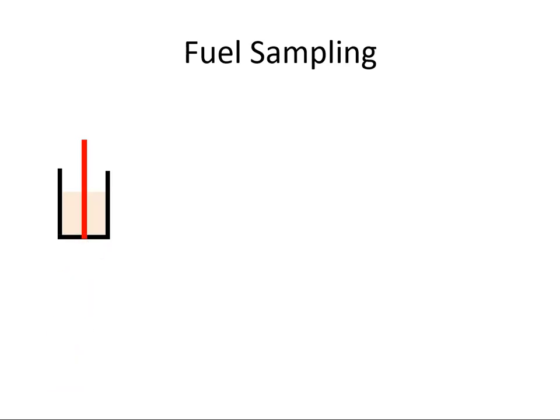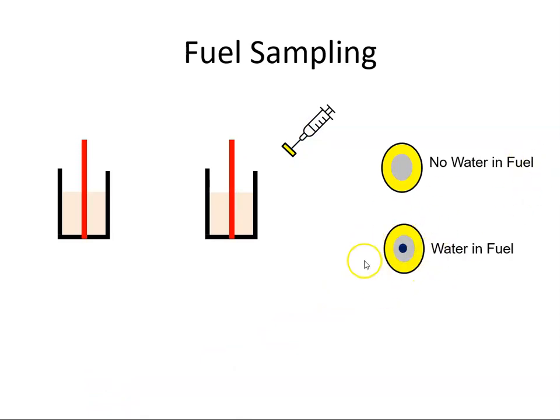If there was no visual indication of water in the fuel, you can do another test with a syringe and a water detection capsule. Put the detection capsule onto the syringe and then into the sample jar. Mix it around and draw the fuel through the capsule into the syringe. If there was any water in the fuel, there will be a dark blue discoloration on the capsule. If there was no water, there would be no discoloration.